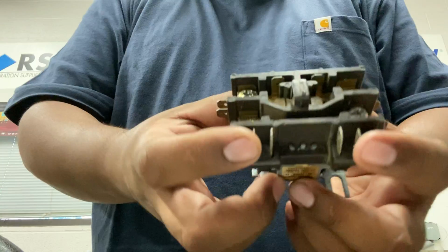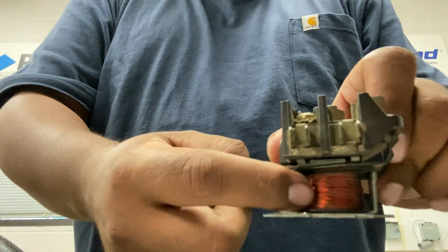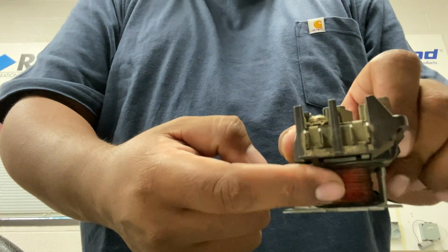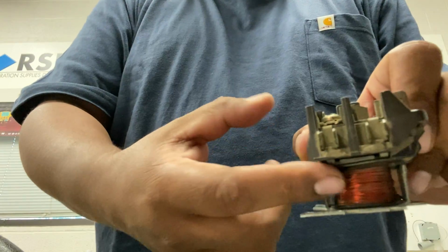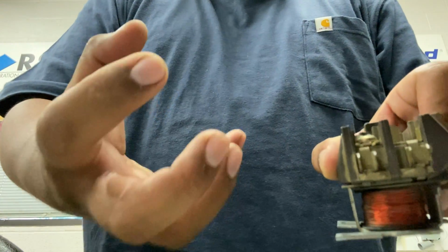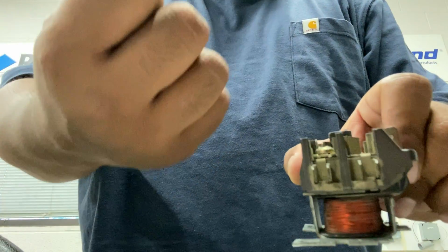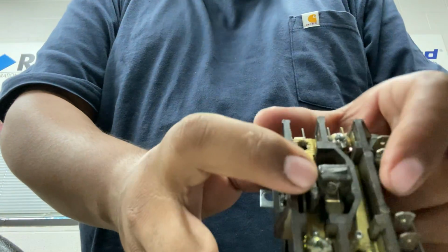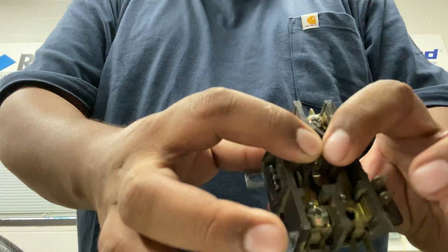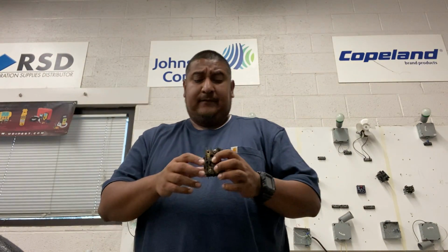So those 24 volts are going to energize this coil here. Now, when we energize this coil with 24 volts, what's going to happen is that coil is going to generate a magnetic field. And that magnetic field is going to pull down on this plunger that sits up here. So once it pulls, it closes the contacts and allows the voltage that's down here to actually travel and come up to the top. And this will actually go and feed a compressor, condenser, or blower motor, whatever the case may be, right? So this guy here is a contactor, right?